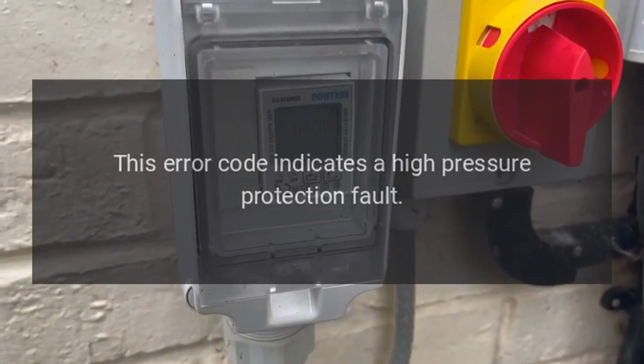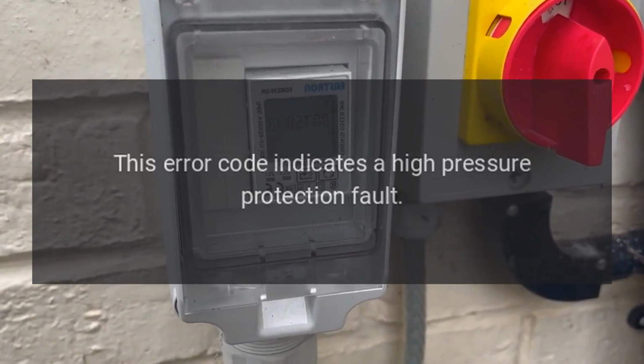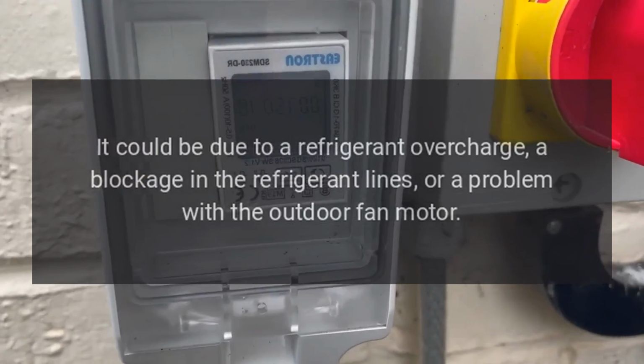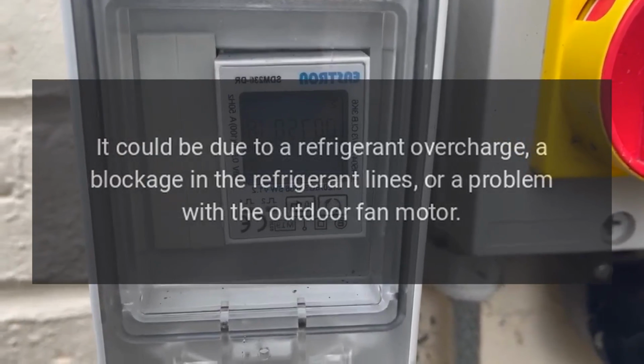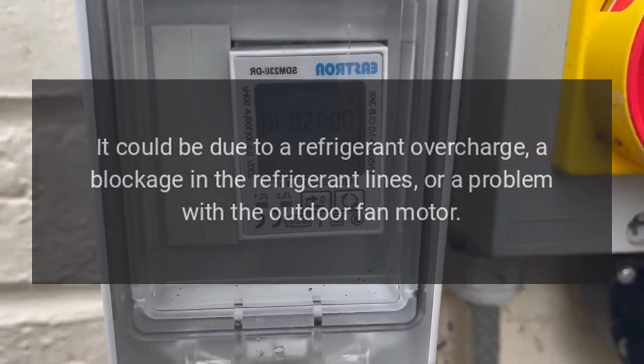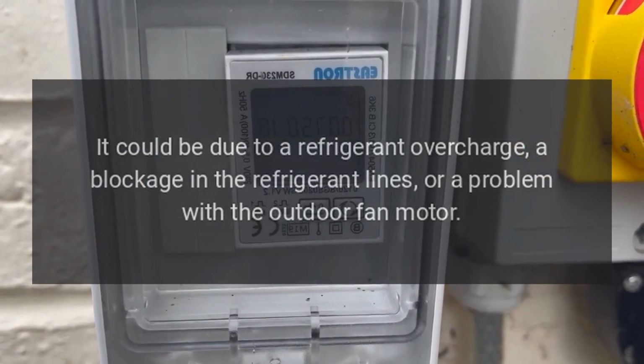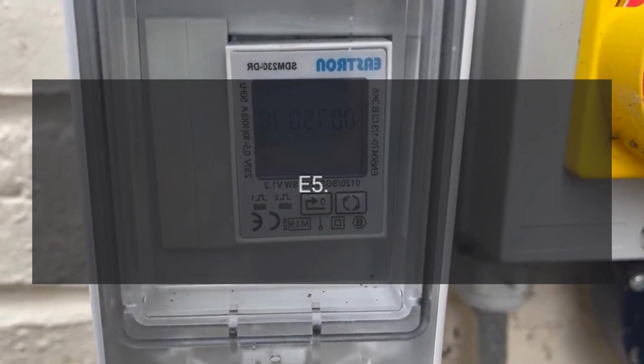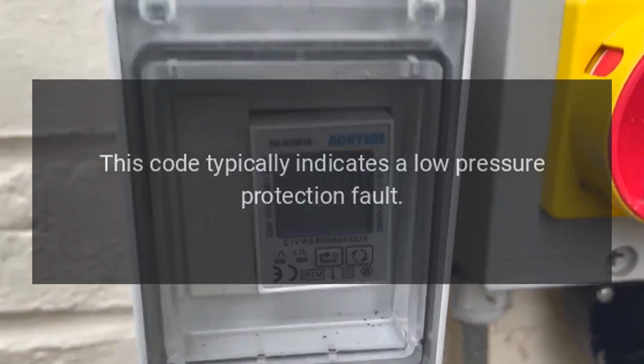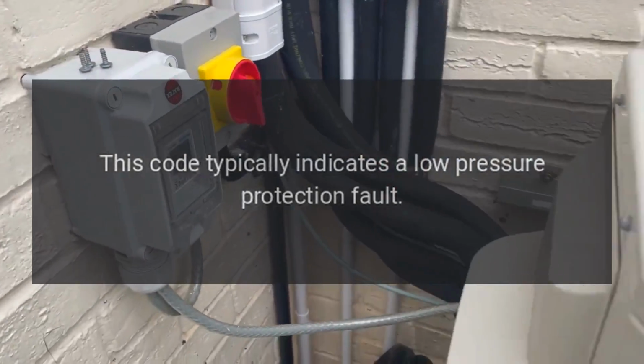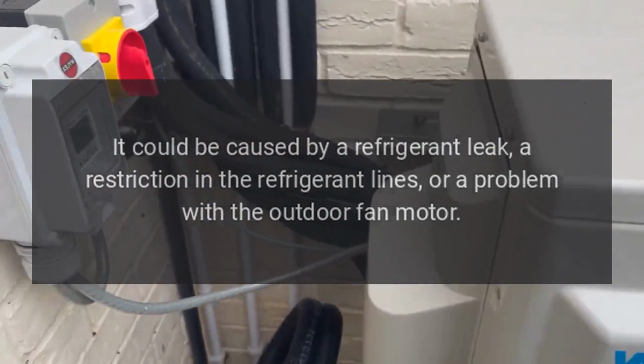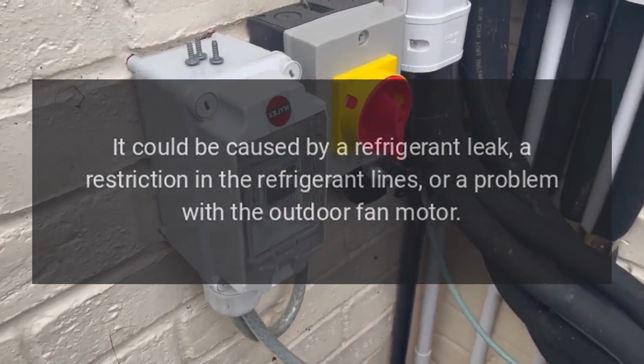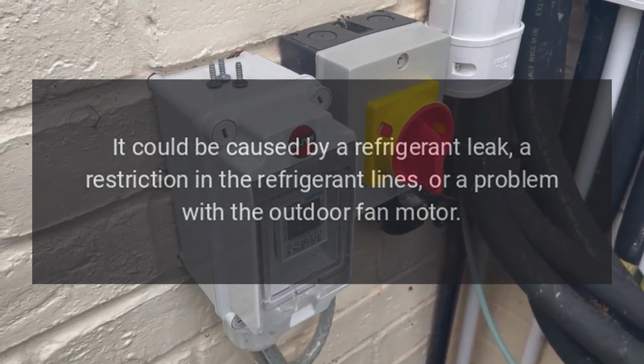E4. This error code indicates a high pressure protection fault. It could be due to a refrigerant overcharge, a blockage in the refrigerant lines, or a problem with the outdoor fan motor. E5. This code typically indicates a low pressure protection fault.